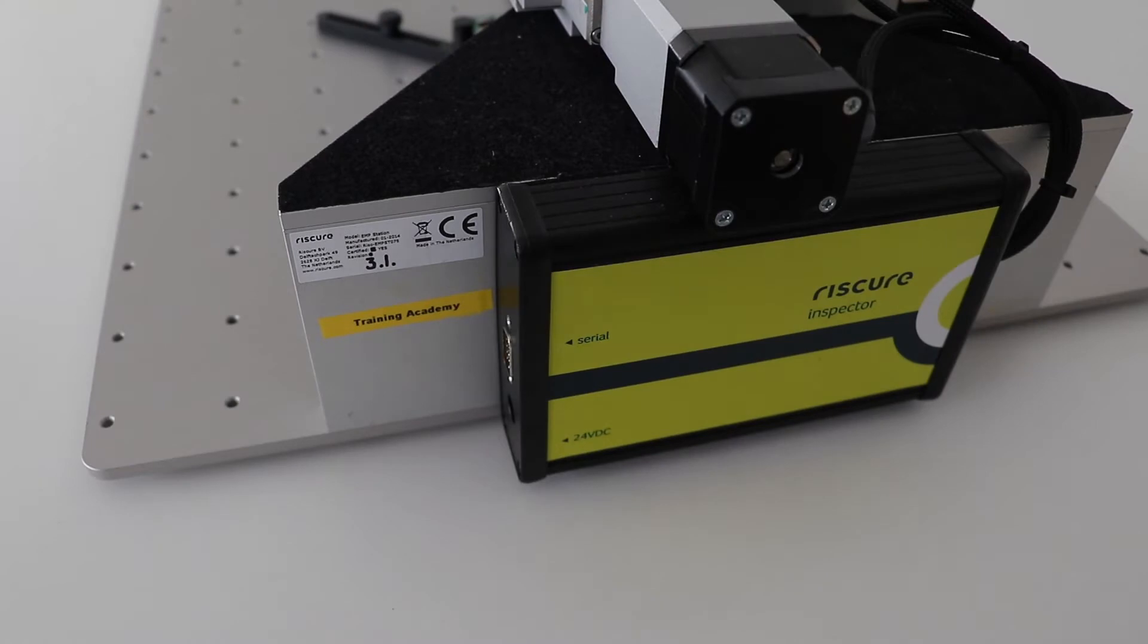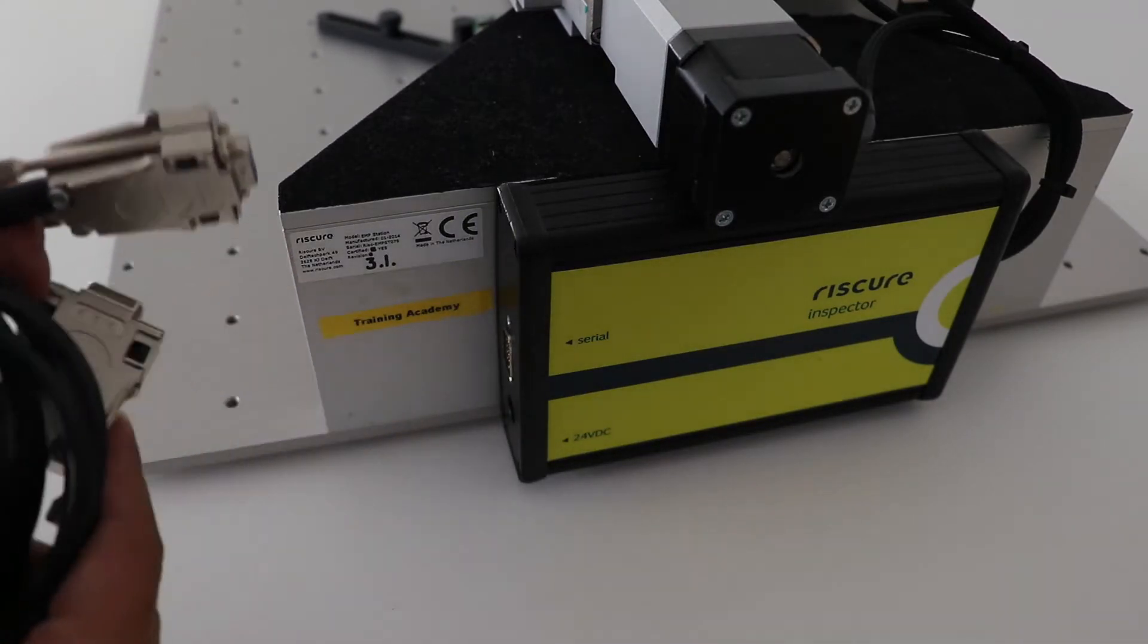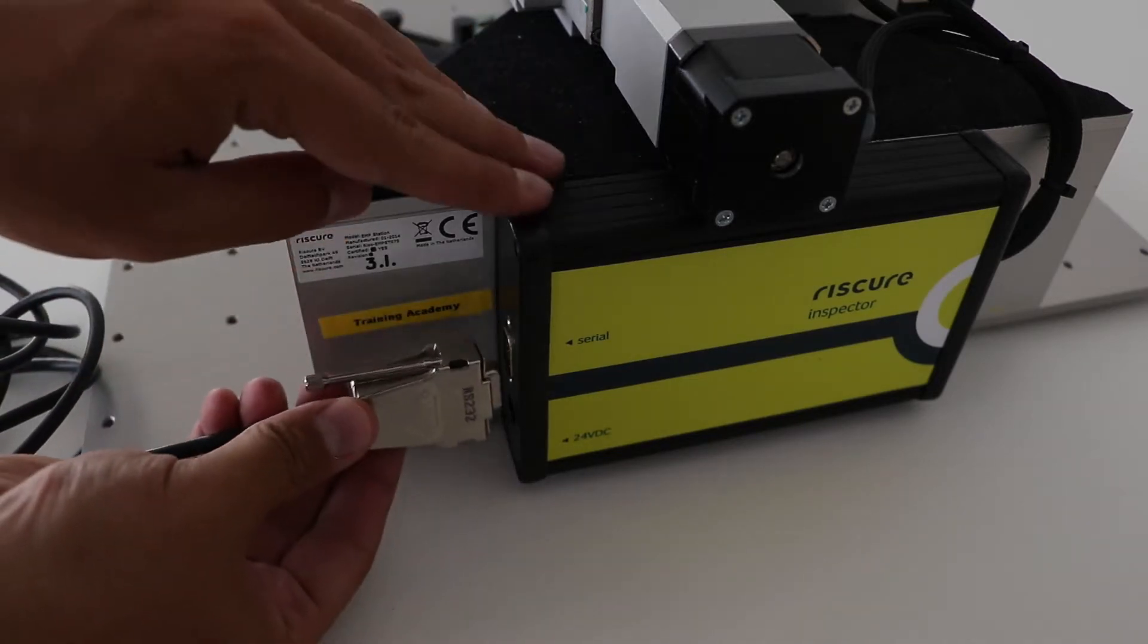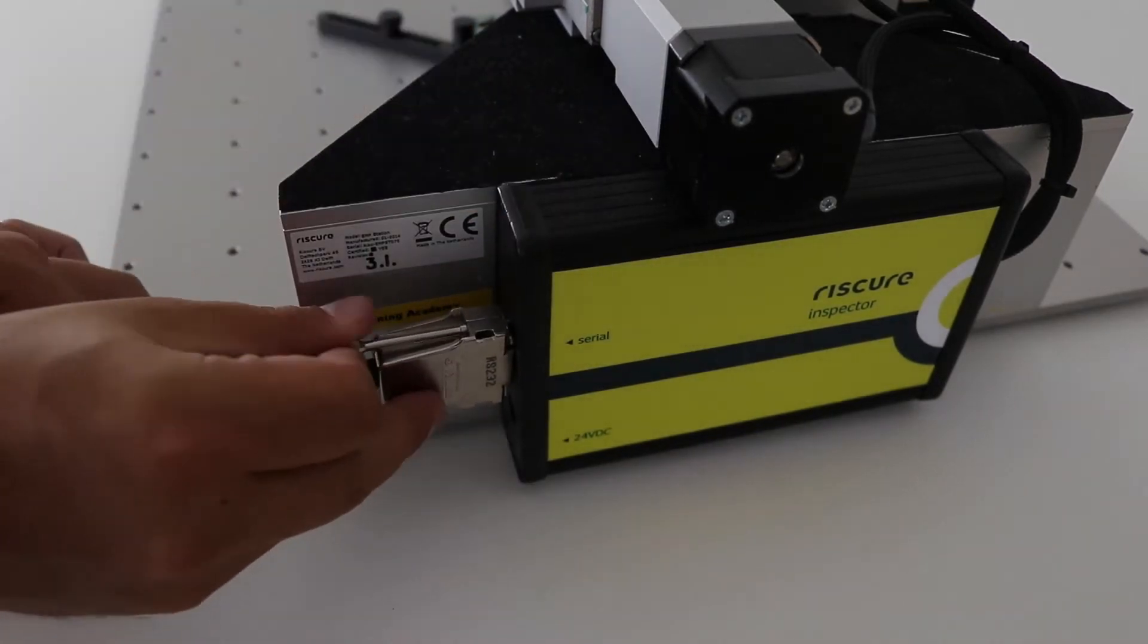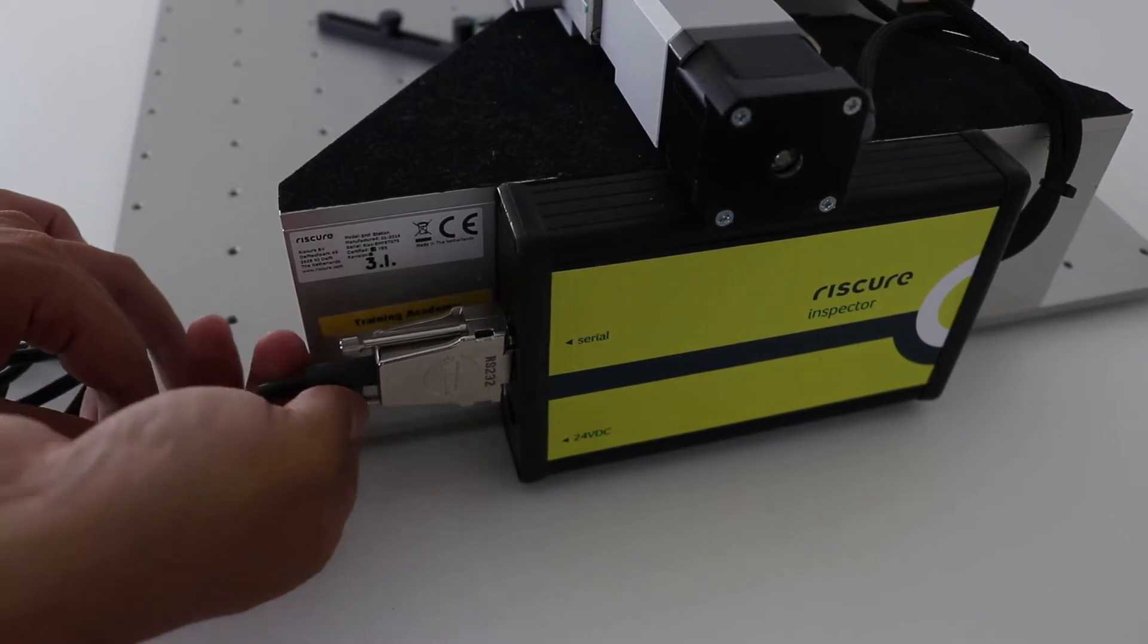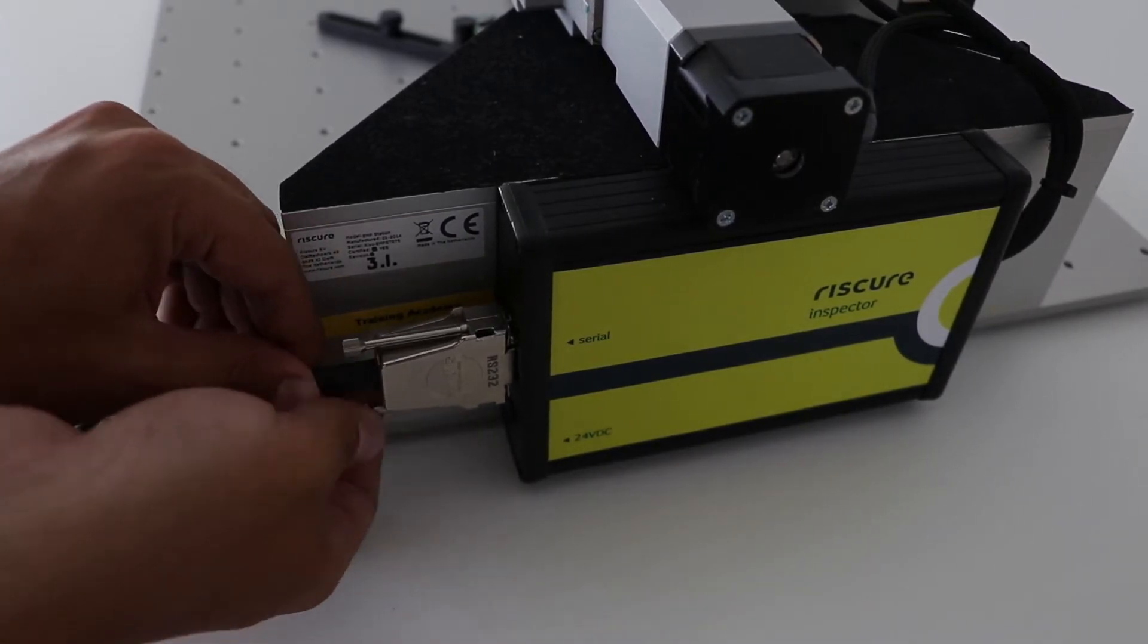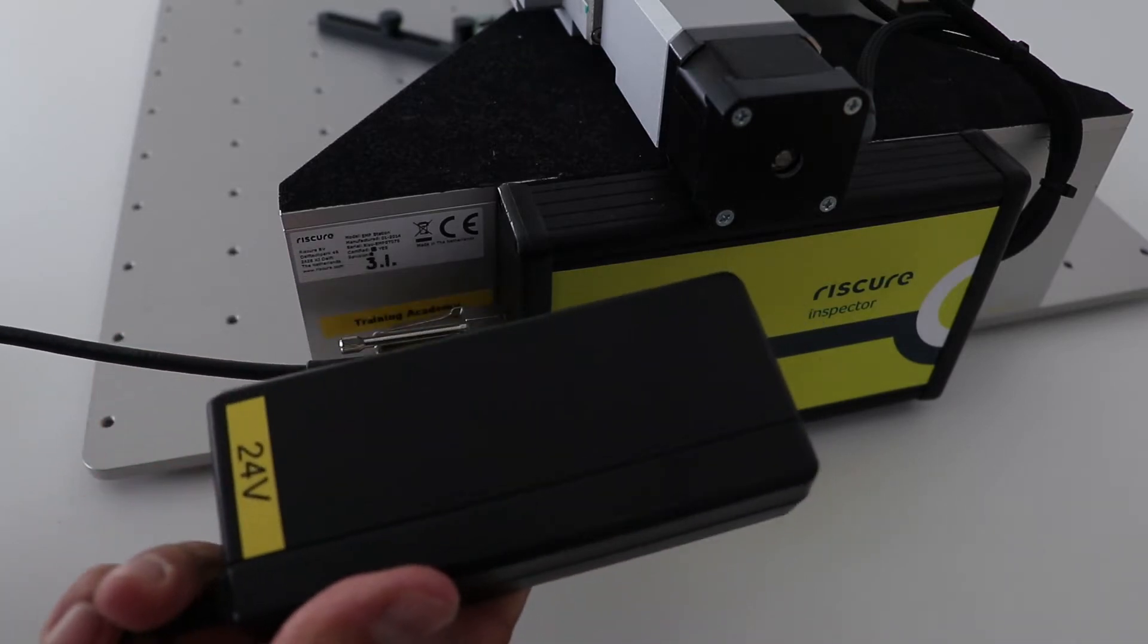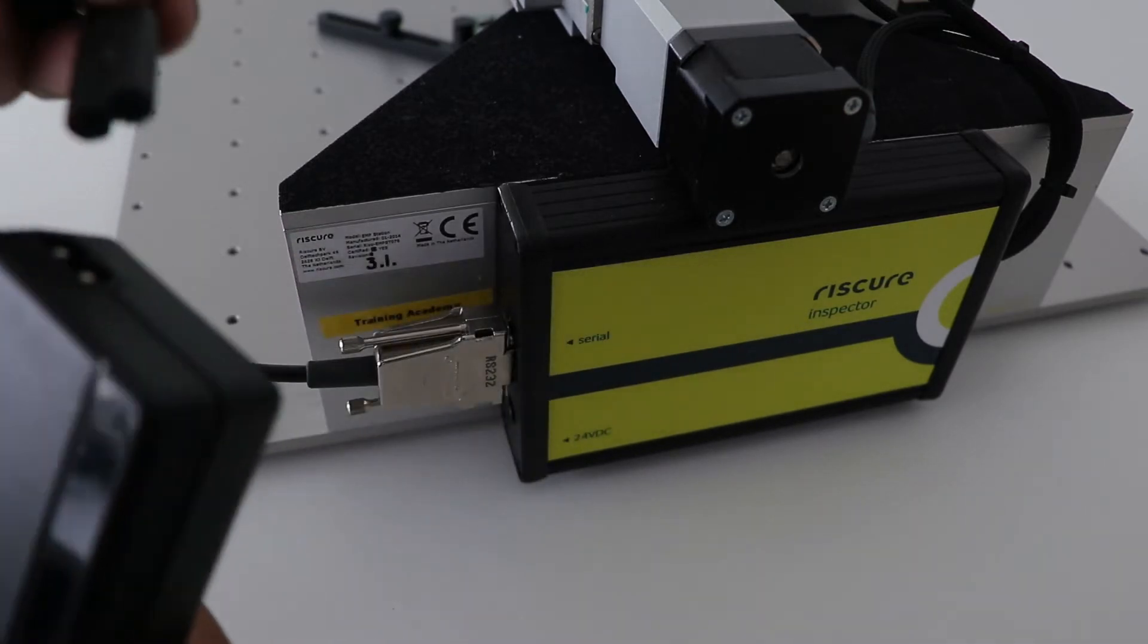To enable the probe station, we use the communication cable to connect it to the computer. And then, we connect it to the power using the power supply unit of 24 volts.